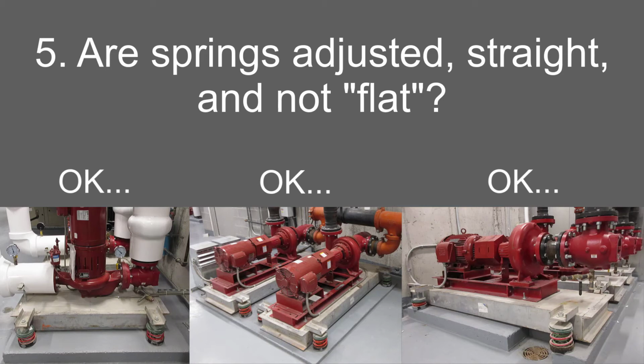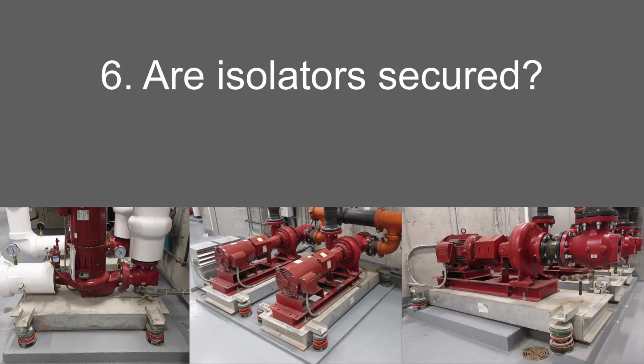Since the suction pipes weren't being supported off the base as accounted for in the isolator selection, they weren't deflecting as far as anticipated, but unless there are noise problems, it's not necessary to change the springs to match the lighter load. The primary thing to ensure is that the bases are floating. Are the isolators secured? Yes, to the inertia bases.